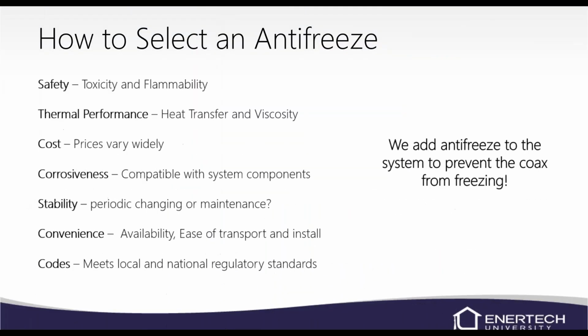Antifreeze in the loop. Selecting antifreeze, that's normally what their codes and that kind of thing are looking at. Obviously, you have to look at toxicity and flammability, the thermal performance, the heat transfer and how thick it is, the viscosity, cost, corrosiveness, stability, convenience, and obviously codes. We add the antifreeze to prevent this system from freezing up. Coaxes are a little bit better about handling freezing. You get into the braze plate or the tube and shell, and those don't handle freezing very well. So we don't want the system to freeze up because it will cause major issues.